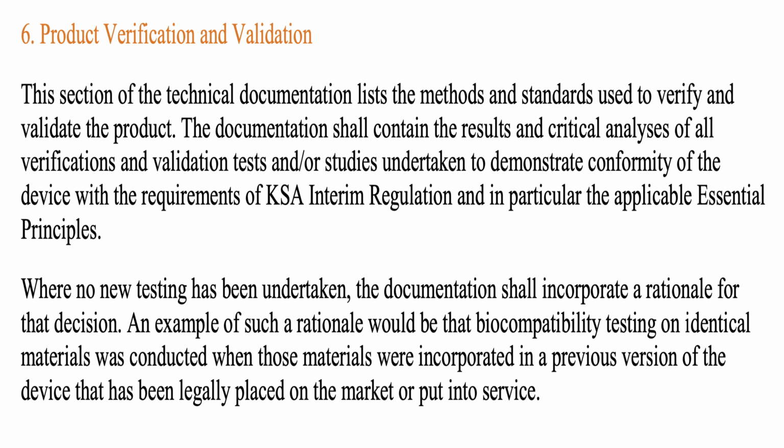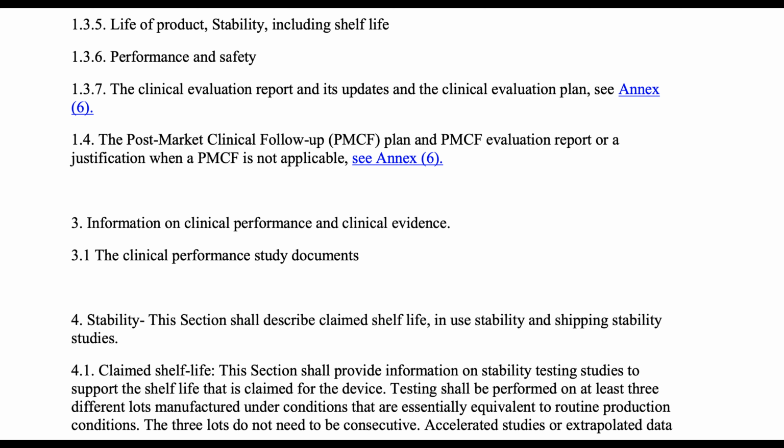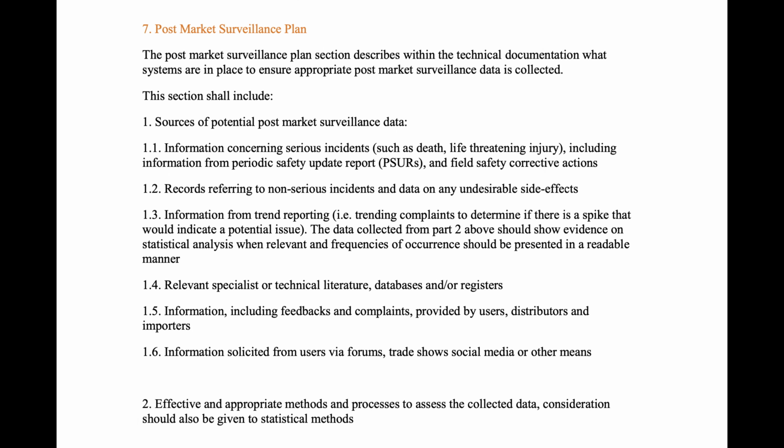Once you do this, then stability data should also be captured. Stability such as the claimed shelf life, right? The real time, the in-use stability, all those things should be there. Point number 7 then speaks about the post-market surveillance requirement. Once your medical device is placed into the market, what data was gathered as the device was being sold to the customer? All this information should be there in your medical device technical documentation file.